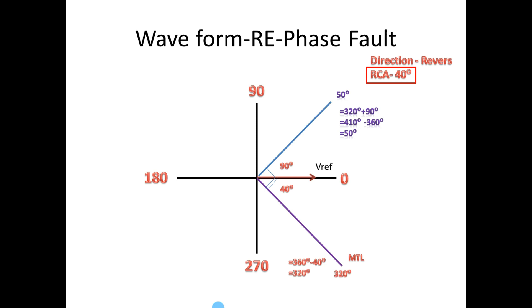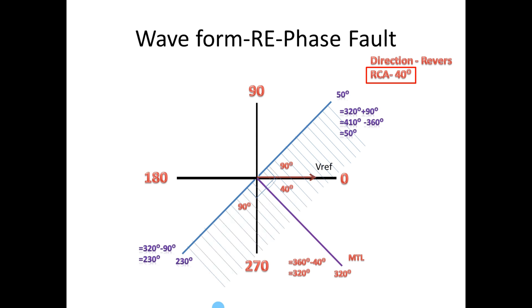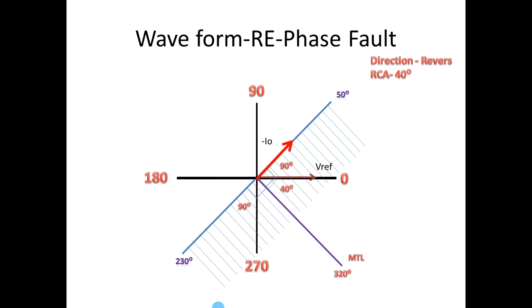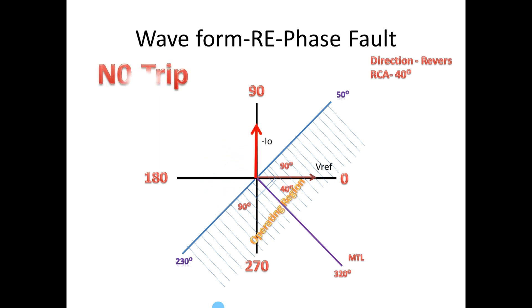Now make MTL as reference and take 90 degrees in the anticlockwise direction: add 90 to 320 to get 410 degrees, which is above 360, so we convert to get 50 degrees — draw a line here. Again make MTL as reference and take 90 degrees towards the clockwise direction: subtract 90 from 320 to get 230 degrees — draw a line here. These two lines are the zero torque line. This is the operating region; the other is the non-operating region. If the fault current is above the pickup value and comes into the operating region, the relay will pick up and give a trip command. Otherwise, even if the fault current is above the pickup value but falls in the non-operating region, the relay will not pick up and will not give any trip.